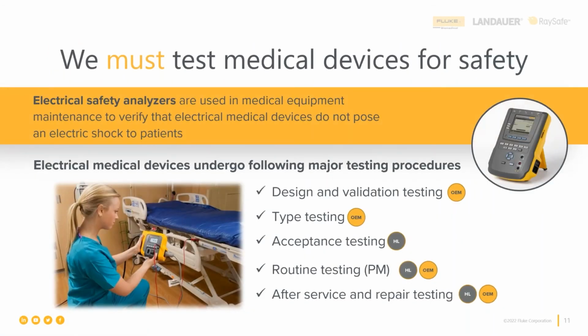So let's take a look at when we do electrical safety measurements. I already talked about acceptance testing. That's number 3 on the check boxes. Design validation testing, type testing means the same thing, and this happens at the medical device manufacturer. When they are finished designing and they think that they have the medical device ready, they will do validation testing that needs to include the electrical safety measurements in accordance with the appropriate standard. And we'll talk about that in a minute.